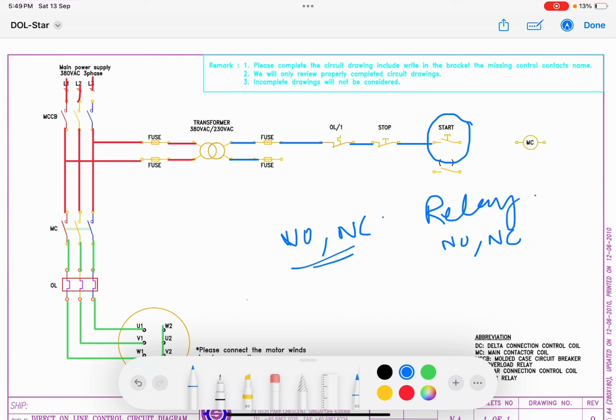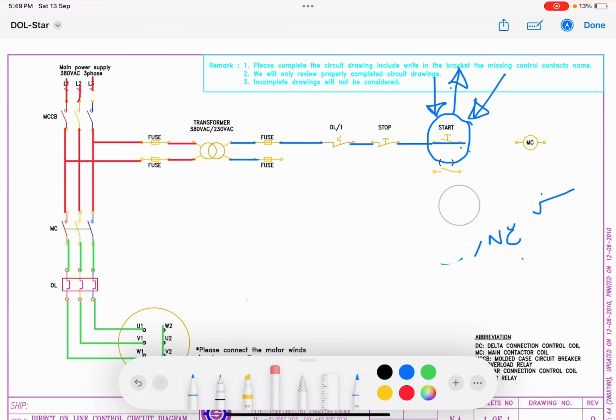So when there is no electrical power given to the coil of your relay, at that condition the contacts of your relay are in NO and NC condition. Same with this start push button, it is a spring loaded start push button. It means that when we are pressing this start push button, only that time is it going to make the contact, and once we release it, it is going to go back to its original position, right? So this is the situation. So right now our start push button is in open condition, which is your normally open condition.